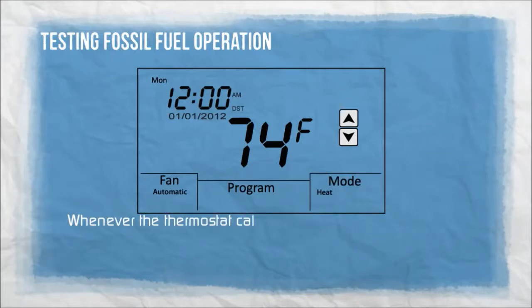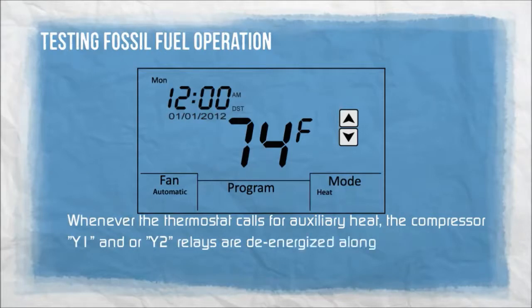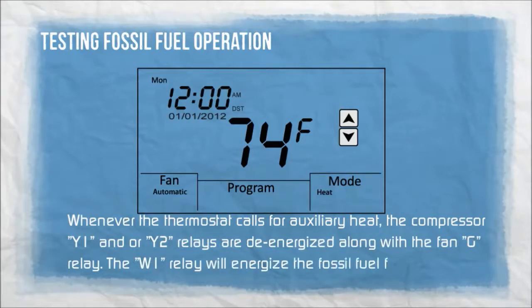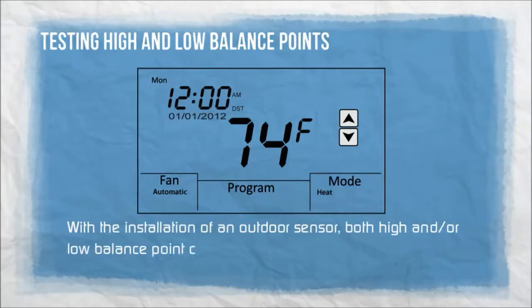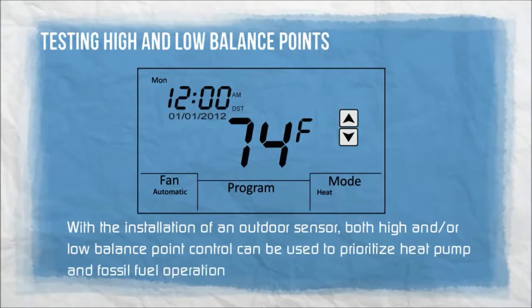Whenever the thermostat calls for auxiliary heat, the compressor Y1 and/or Y2 relays are de-energized along with the fan G relay. The W1 relay will energize the fossil fuel furnace. With the installation of an outdoor sensor, both high and/or low balance point control can be used to prioritize heat pump and fossil fuel operation based on a selected outdoor temperature.